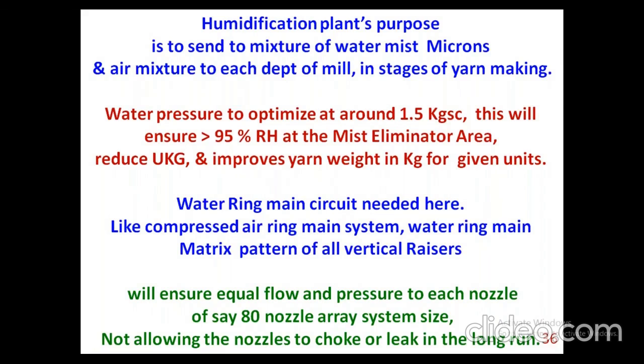If the air mixture is reaching different parts of the mill premises like the ring frame area, the blowroom area or the autoconer area, you can still maintain the water pressure at the humidification plant around 1.5 to 3 kg, depending on the nozzle size, depending on the individual nozzle flow and pressure. You can maintain the header pressure of the nozzle, that is the riser. On the risers, you have the risers. Now you maintain the pressure in such a way that you achieve that 95% RH at the mist eliminator area.